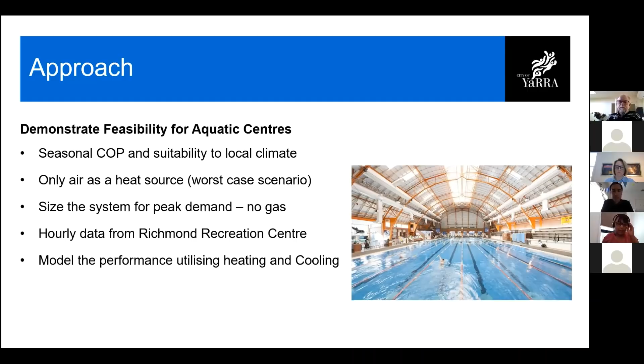For the heat demand, we used hourly data from our Richmond Aquatic Center, which is pictured here. As you can see, it has a humongous pool hall. It used to be an airplane hangar. It's very leaky and old and has a lot of glazing, so we are definitely using more heat than we need to, but that's currently what we have. Because of multiple energy efficiency projects and energy performance contracts a few years ago, we ended up having extensive submetering infrastructure in the building, covering every aspect. We have submetering on the HVAC, on the heating, on gas, on water, on everything. From there, we were able to build a real profile of the energy levels that we are using for our building, and test whether we can meet that demand using a heat pump.